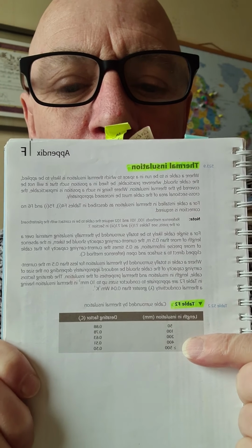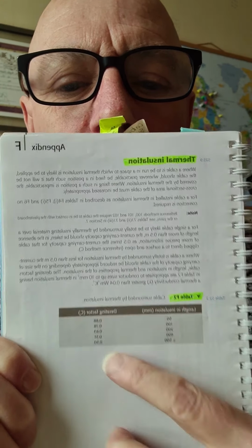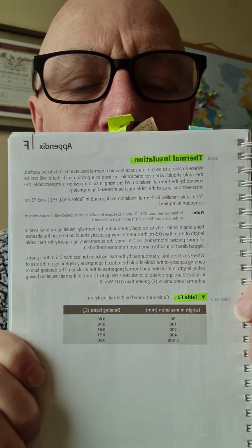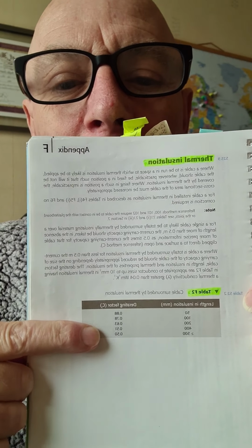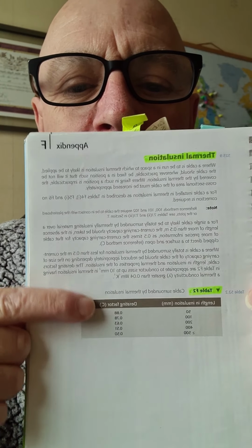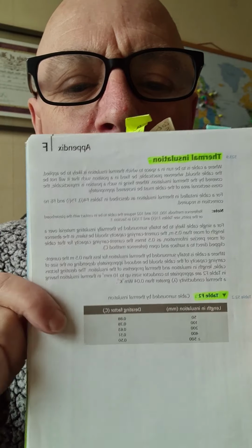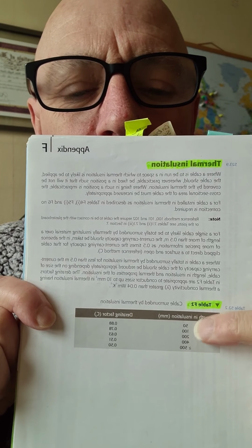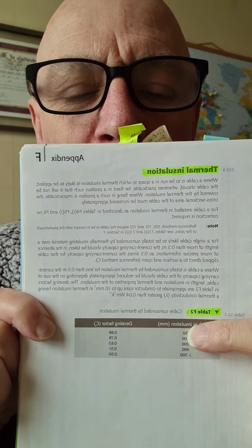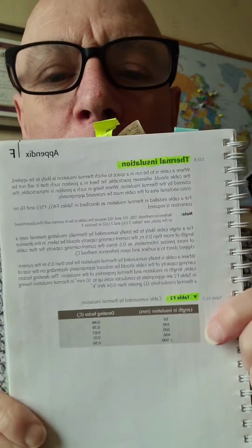One of the most important things to take into account here is that if you've got over 500 mil, so half a meter of insulation, then the rating factor remains the same at 0.5. So that's a good one to try and remember if you know that you've got more than 500 mil of insulation. But otherwise you've got the other ones there, even for just short runs of cable under insulation or touching insulation. It will affect the amount of current that your cable can carry. So it's a really important one to take into account.